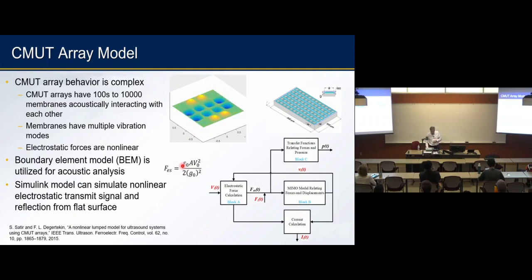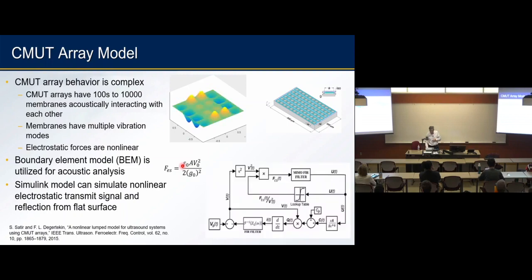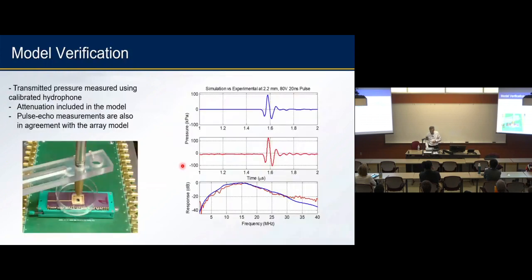And for that, we actually use Simulink to develop that model so that we can predict large signal, when I actually swing the membrane a lot, versus small signal, when I'm just receiving a small vibration. So that we have the full capability of designing these devices, because without a model, you cannot really predict and design a high-performance device. So with that model, we were able to predict, for example, the pressure output at a certain distance, and this is the measurement, and we can actually fit the curve on it. So after around 10 years or so, we now had a good model to predict the complex behavior of this type of device. So with that, now we can go ahead and design devices.